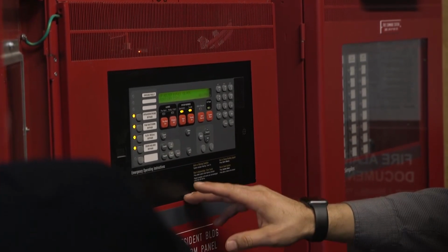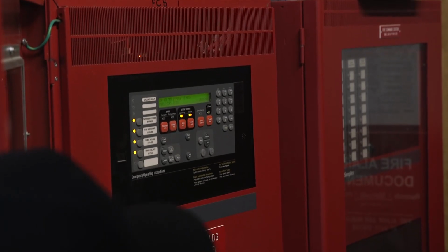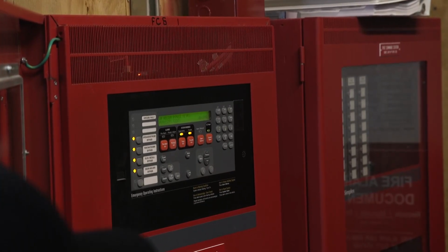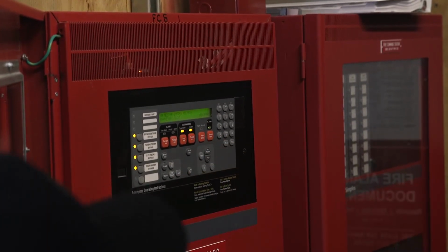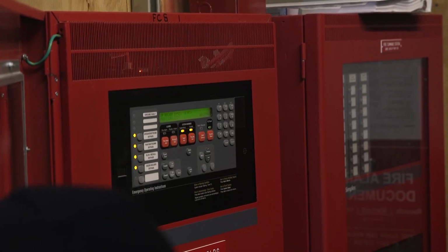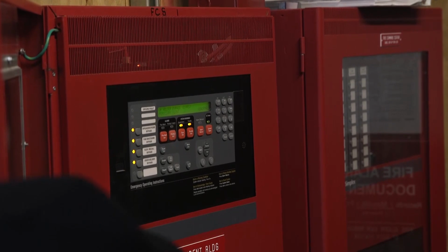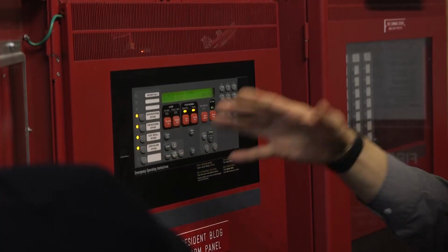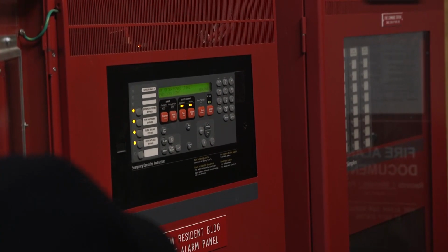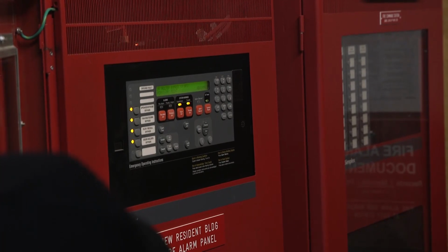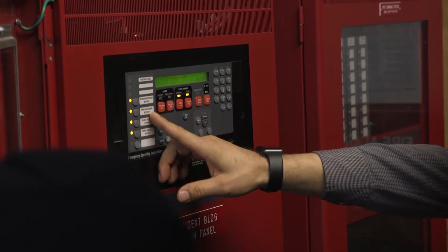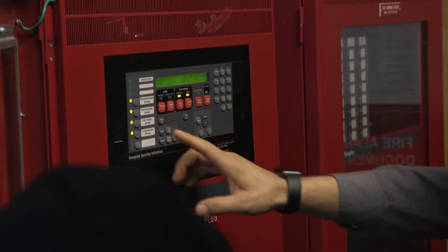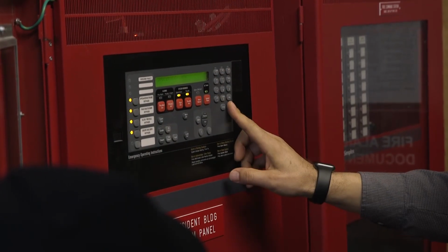So for example, when this is bypassed, it's still gonna come as alarm. Your panel next door will see it as alarm. When in a walk test, you're not gonna see it as alarm, it's just a trouble. That's the difference. So you can bypass, but you still receive a real alarm. And to unbypass this, you also need to be on level 3, because if you're on level 1, you cannot unbypass this. You need to log in also.